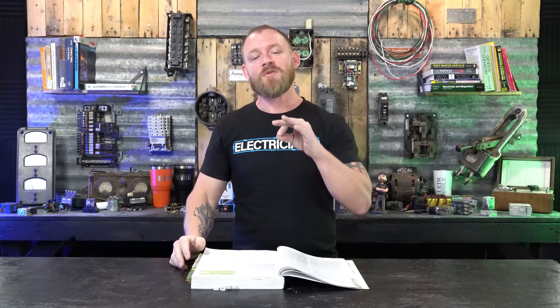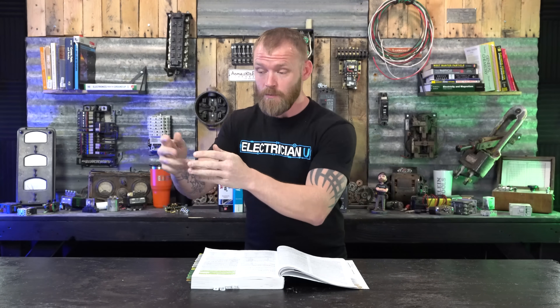The problem is most people aren't electricians, don't know electrical code, and when they're cold in winter they just plug in a bunch of stuff. They might plug two space heaters into the same receptacle, drawing around 21 amps. You'd think a 20 amp breaker would trip — but not necessarily.